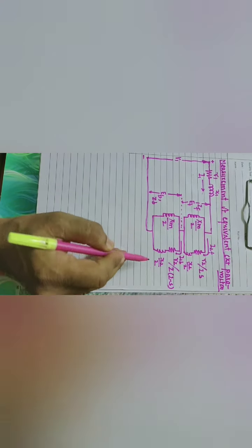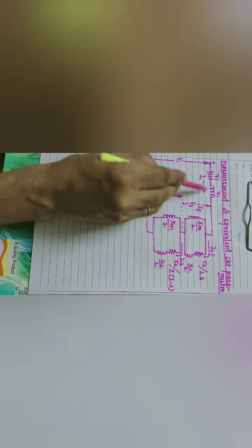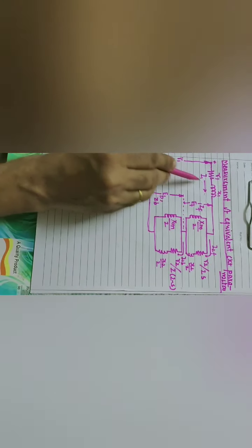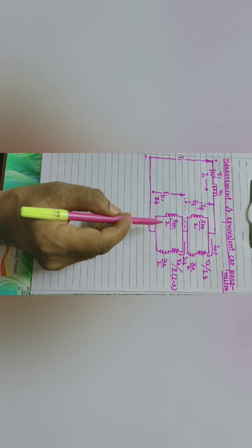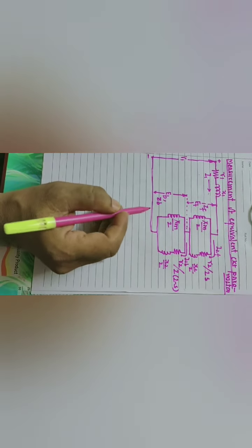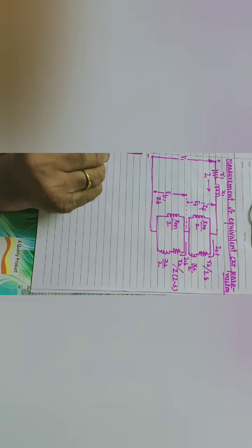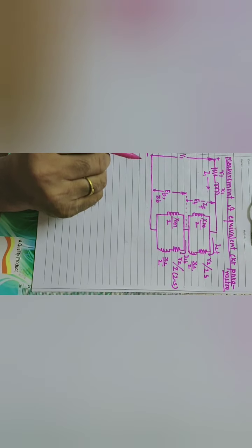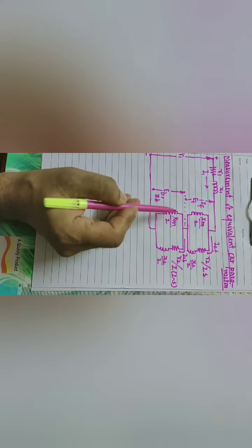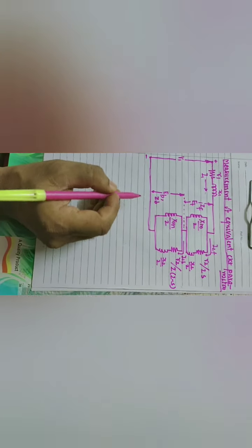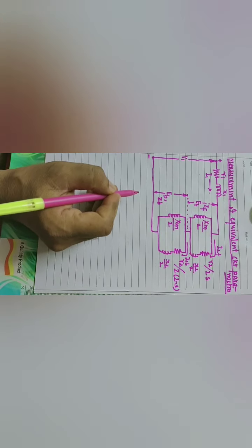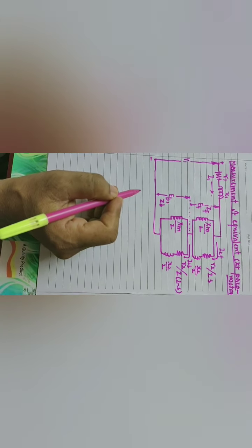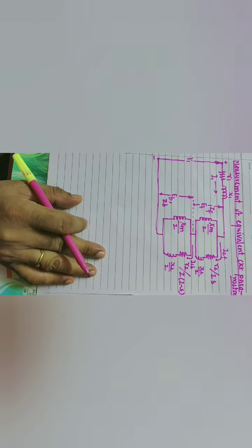In the laboratory, we have to measure the equivalent circuit parameters. All these parameters we have to measure by taking tests. So generally 3 tests are required. One is the stator resistance test to determine R1. The second test is the block rotor test, and the third test is the no load test. So using these 3 tests we can determine all the parameters of the equivalent circuit.